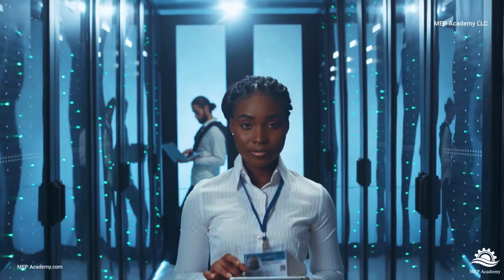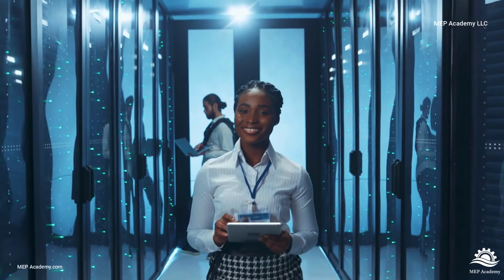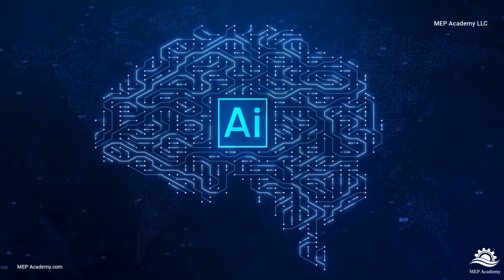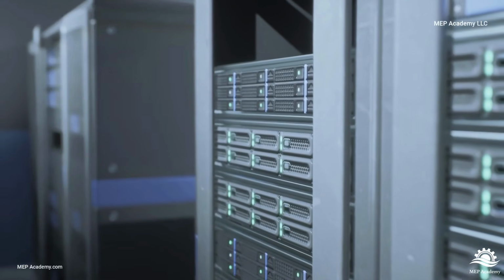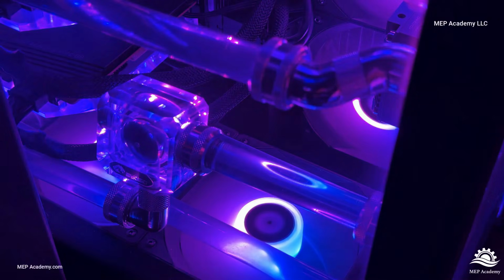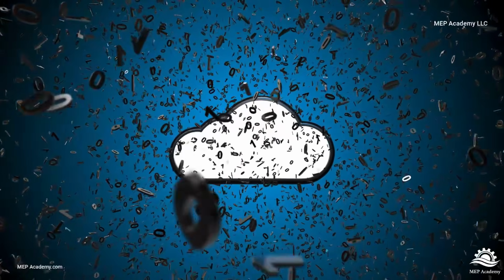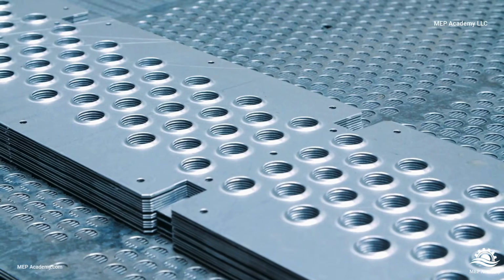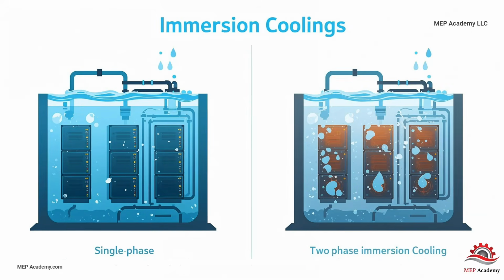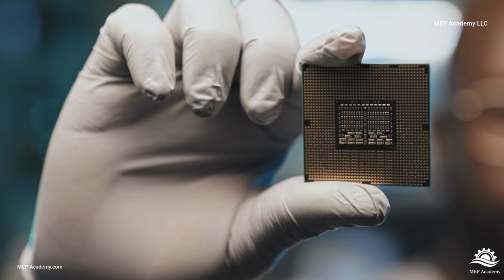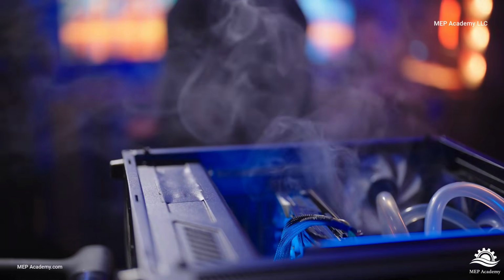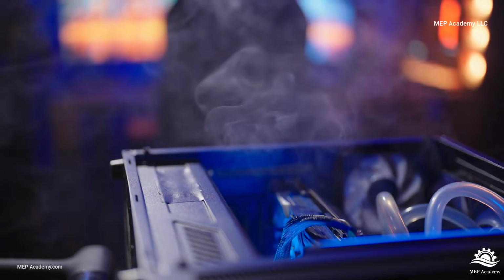For decades, air cooling was the backbone of the data center industry. But artificial intelligence is changing the rules. As rack power densities continue to rise, liquid cooling is becoming one of the most important technologies enabling the next generation of AI computing. Whether it's direct-to-chip cooling using cold plates or full immersion cooling using dielectric fluids, the goal remains the same. Remove heat more efficiently so processors can operate at higher performance levels. And as AI continues to expand, liquid cooling will likely become one of the defining technologies shaping the future of data centers.